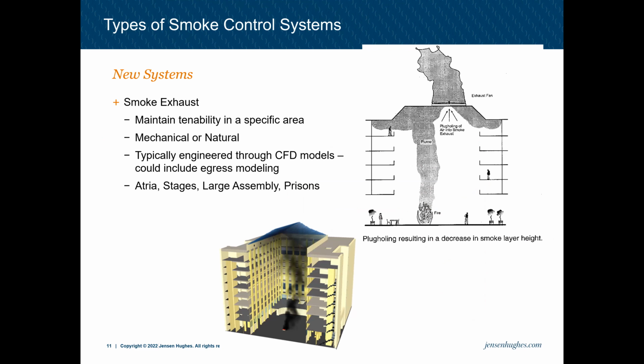Our other type of system is a smoke exhaust system. A smoke exhaust system is what it is in the name, where we're taking smoke outside of a space. It's designed to maintain tenability in a specific area. The term tenability means basically, can you live in the space long enough to egress or walk out of the space? We usually look at tenability in terms of three different criteria: temperature, visibility, and carbon monoxide yield.